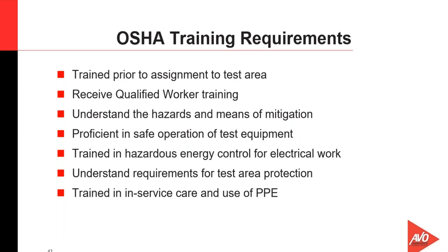Proficient in safe operation of the test equipment. I understand the equipment. I understand all the issues associated with the equipment. I understand the hazards involved in using the test equipment, and have demonstrated that, and also know when the equipment needs to be shut down and when to hit the e-stop. Trained in hazardous energy control for electrical work, which means switching, clearing, locking, tagging, LOTO, or switching and clearance procedures, whichever we're working, whether we're working in utilization or industrial power, either one. So that's a significant thing. And in the testing environment, we find that a lot of issues actually occur because of verification and inappropriate switching and clearing. So that's where a lot of these things actually occur.